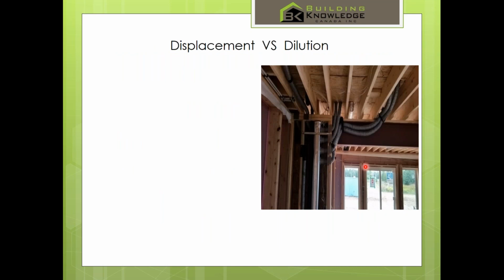We have to start to understand the difference between displacement and dilution. Displacement is the method of conditioning we've been using for 30 to 40 years plus in the residential market, and that is air that comes out of a register. It comes into a room and it displaces air, and the displaced air magically goes down the return. The return does not pull the air around the room. The register does not throw air around the room. It is heating by displacement. Dilution is heating or cooling conditioning by mixing the air in the room.